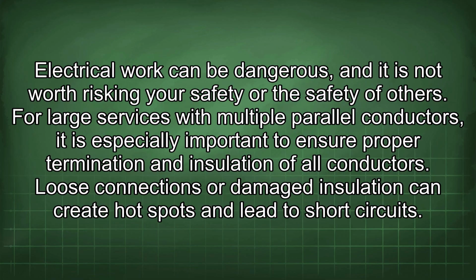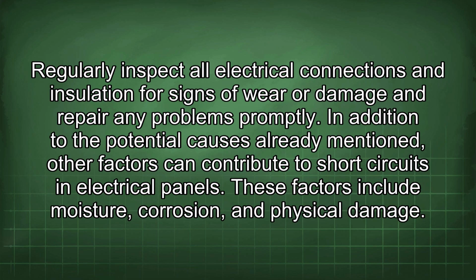For large services with multiple parallel conductors, it is especially important to ensure proper termination and insulation of all conductors. Loose connections or damaged insulation can create hot spots and lead to short circuits. Regularly inspect all electrical connections and insulation for signs of wear or damage and repair any problems promptly. In addition to the potential causes already mentioned, other factors can contribute to short circuits in electrical panels. These factors include moisture, corrosion, and physical damage.